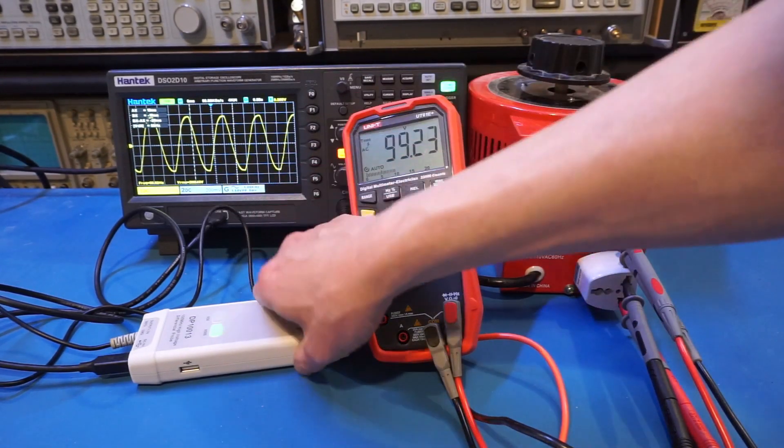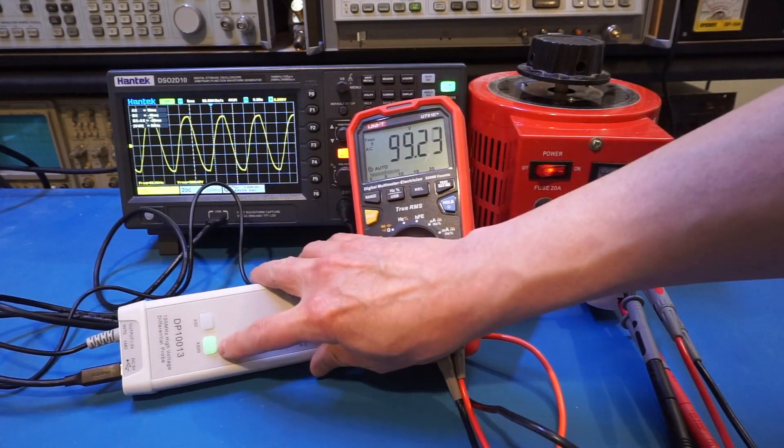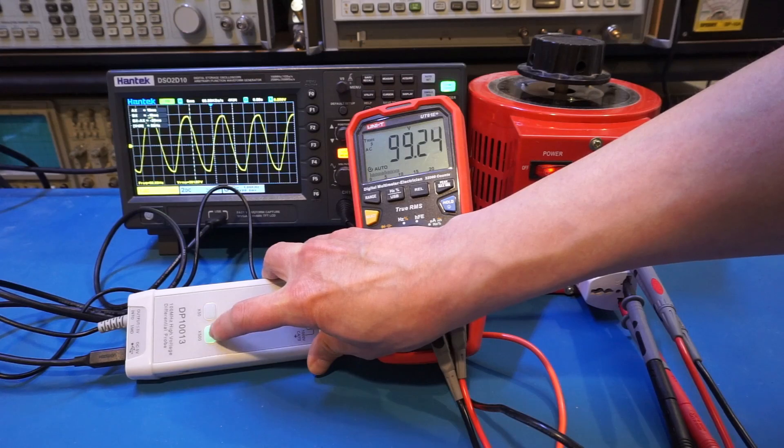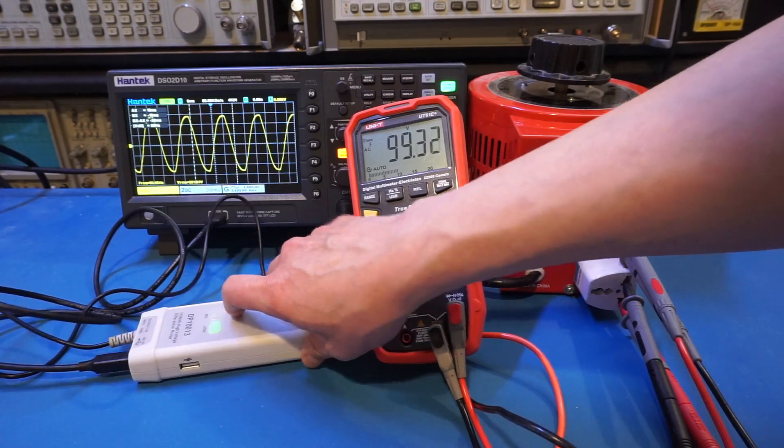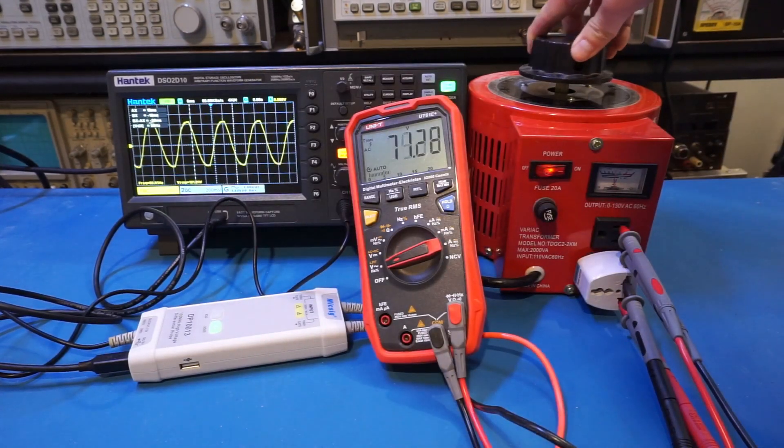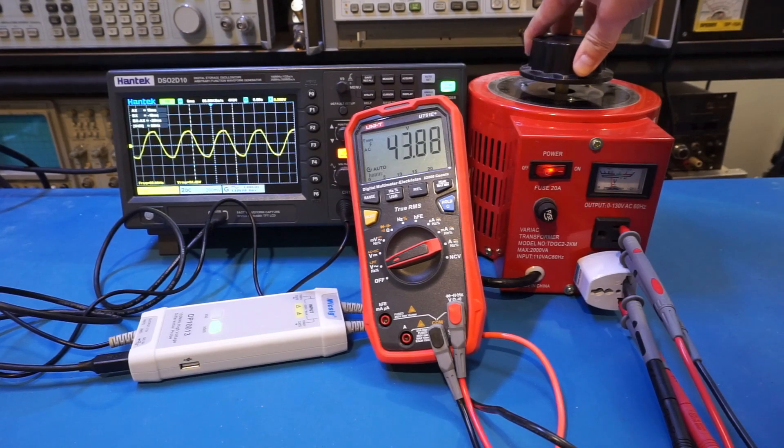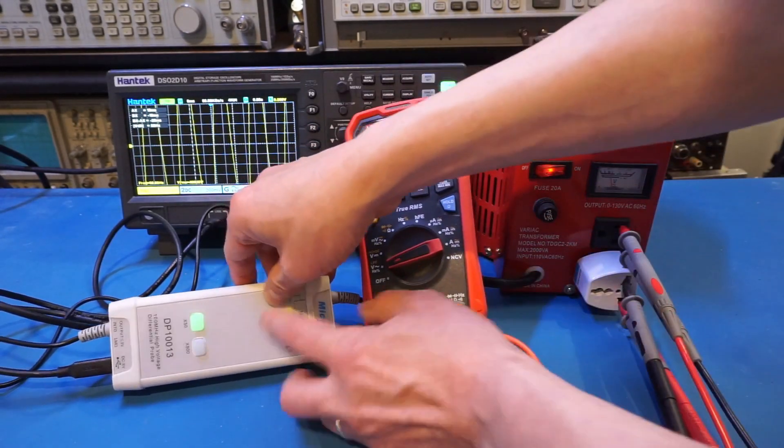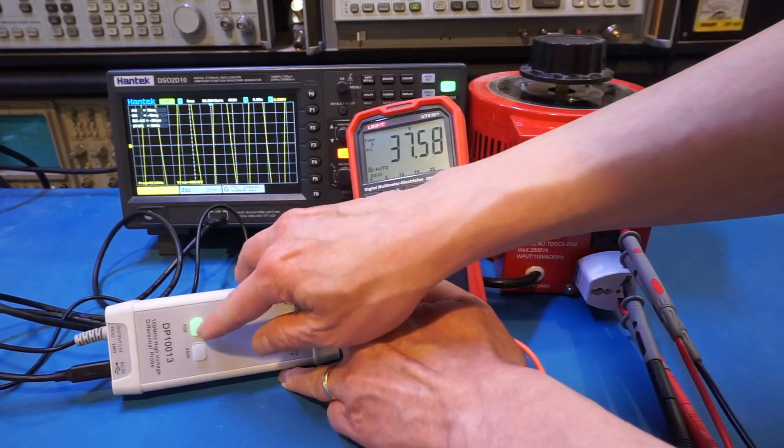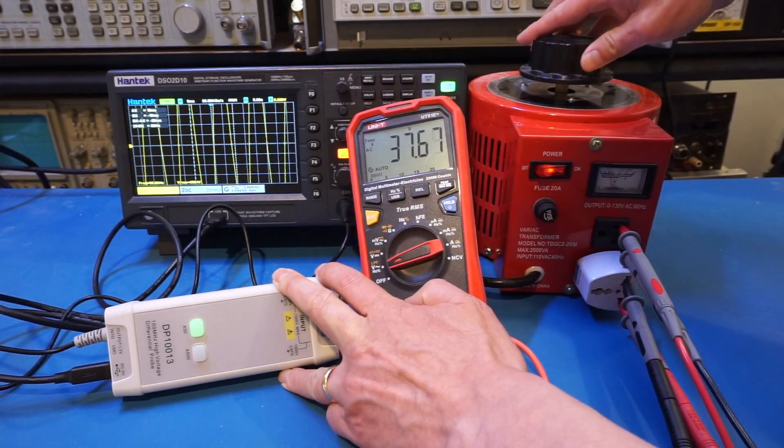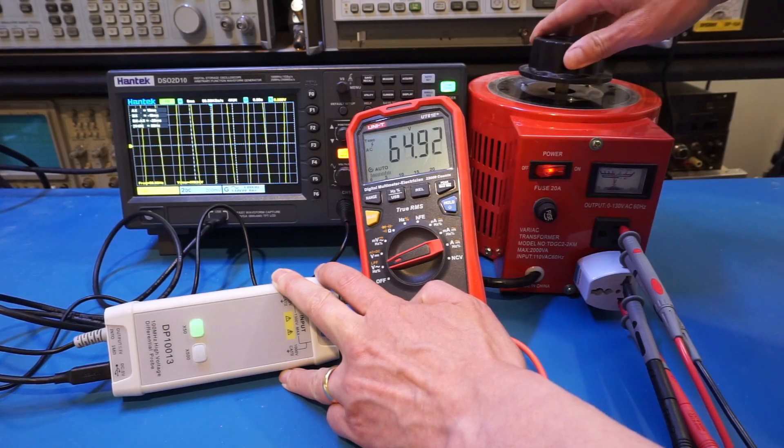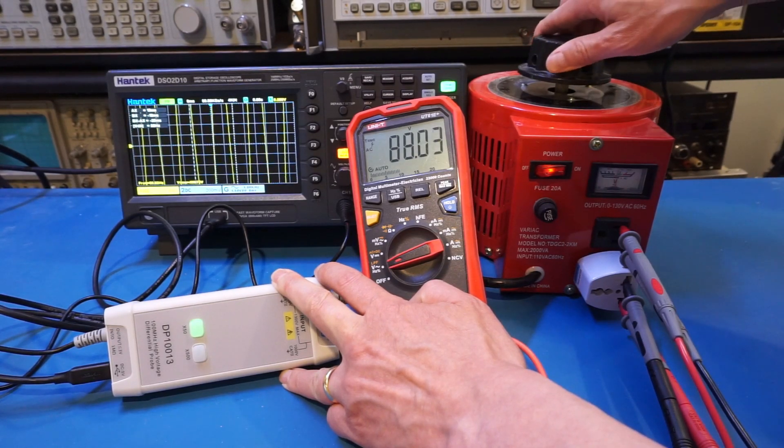This differential probe also has a feature where you can see that this light right now is green, it's indicating we're in this times 500 setting. And if I lower the voltage, I'll show you that we can change it to times 50. And what happens is if the voltage is above the range, it will start to flash, indicating that you need to dial down the voltage, otherwise the probe might be damaged.